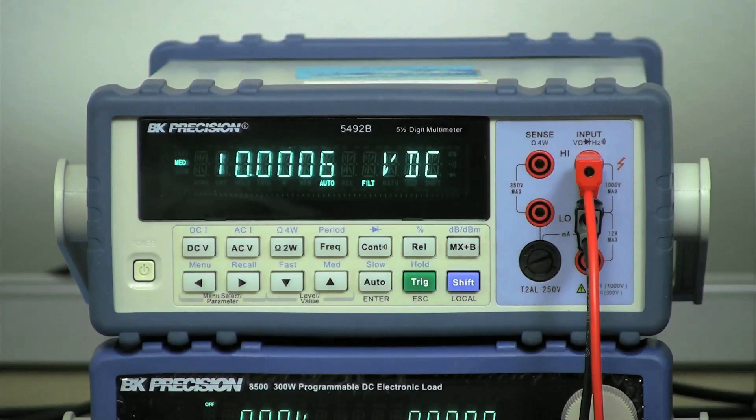This reading will be the no load voltage, or the voltage with zero current load. Keep the power supply output on.